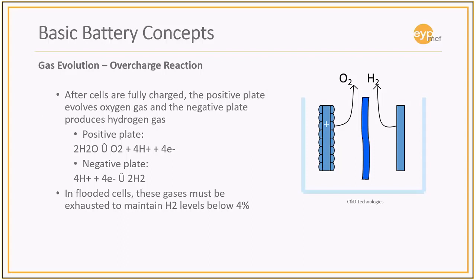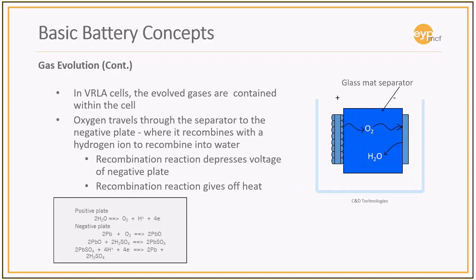Gas evolution: as batteries charge, they tend to produce hydrogen, especially flooded cells. So we monitor the room to make sure we don't get a lot of hydrogen, and if we do, we have exhaust fans to deal with it. More and more authorities having jurisdiction are requiring ventilation in valve-regulated rooms, as well as sometimes even direct ventilation of the battery cabinet itself. It's hard to explain why the interpretations vary from location to location. You try to educate the local authority as best you can, but ultimately you're stuck with whatever they decide you have to do. So there's always that chance you may have to provide ventilation, and even hydrogen detection, in a valve-regulated environment.